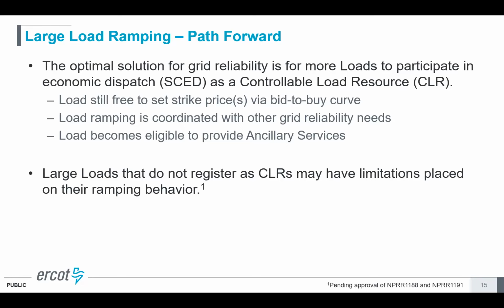So you're no longer having to use your frequency regulation to cover ramping behavior that is driven just by a desire not to consume at high prices. We think that's a good path forward. Depending on how many loads move into that bucket of controllable loads, we may also have to limit the ramping behavior of loads that elect not to do that, because it presents a growing risk to frequency control.